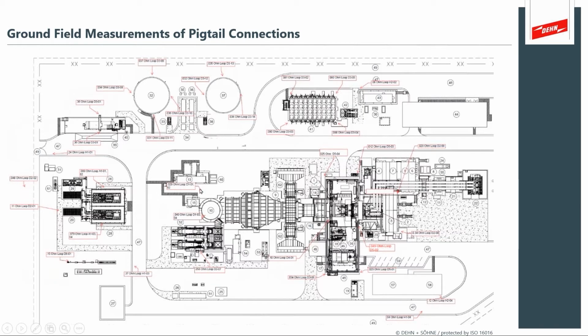We can inspect using those clamp-on meter methods where you can actually determine that the impedance at each of those pigtails is suitable and gives you a very low impedance connection to that large earthing grid. And so what that measurement system allows you to do is to inspect the pigtail connection to tell you that the buried connection and the above grade connection are both suitably bonded and in proper working condition, so that the customer has a very strong and a very clean impression of the earthing system that's actually all buried.